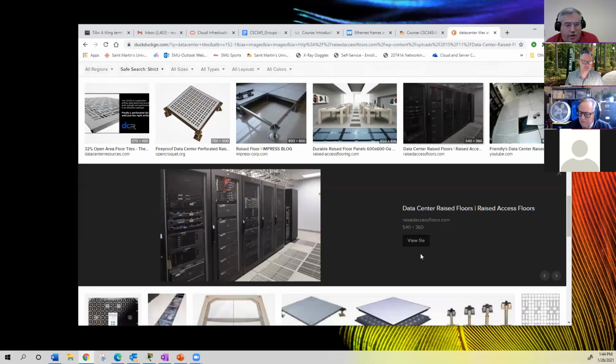In our data center in Louisiana, we had a very similar setup to what he's talking about here with the raised floor. One time the cooling went out on it, and the data center hit about 100 degrees within about 15 minutes. It was not a good plan, but we had to open up all the doors to the data center and put box fans basically to try to blow cool air in there. Got it down to around 80 degrees until the AC guy could come and fix it for us. Yeah, that's exactly right.